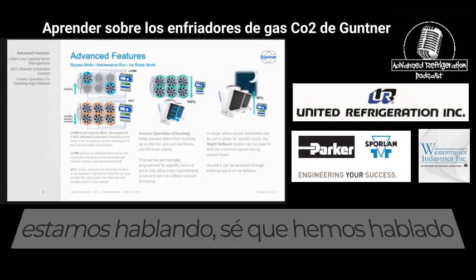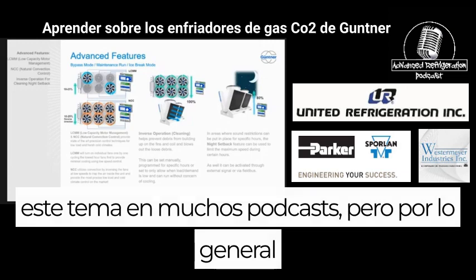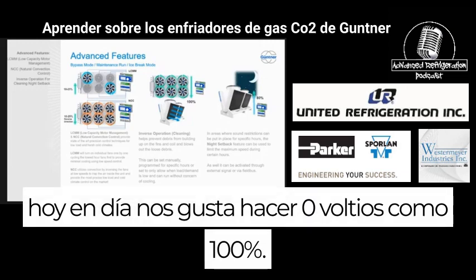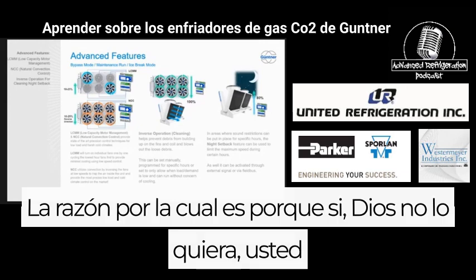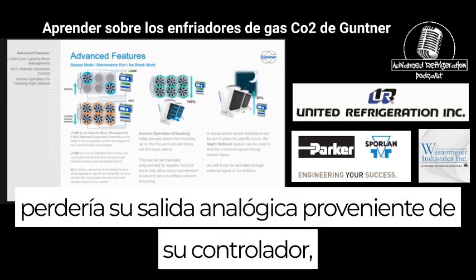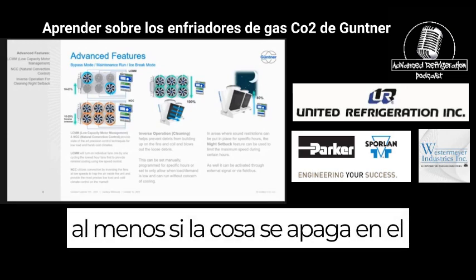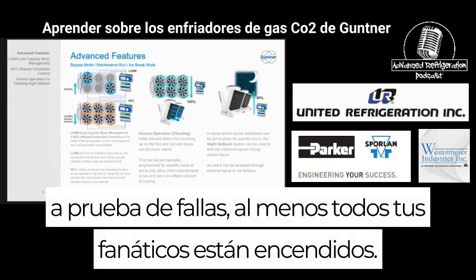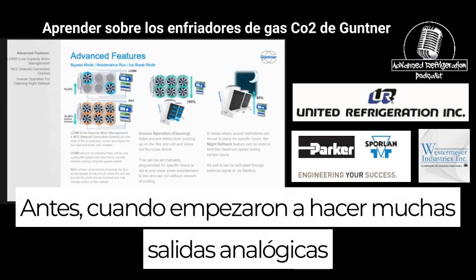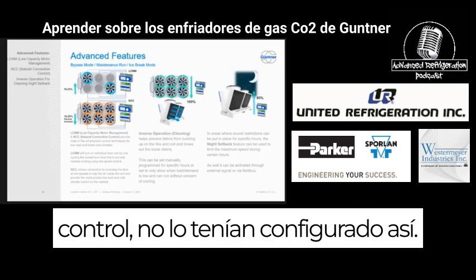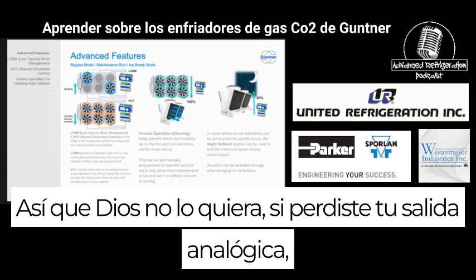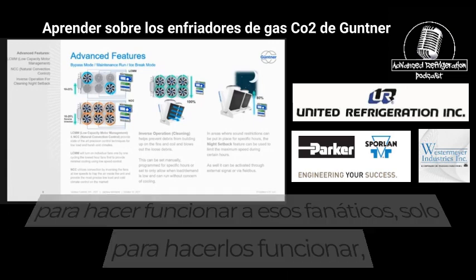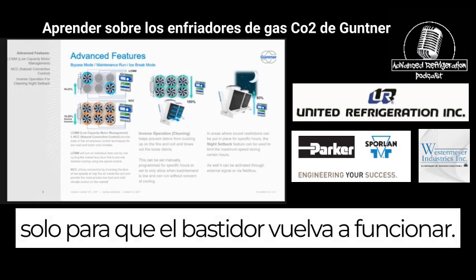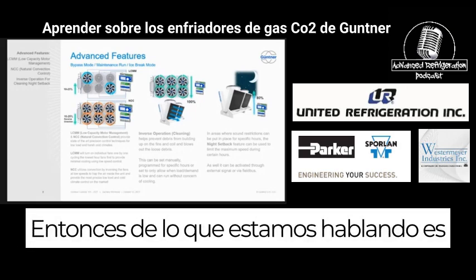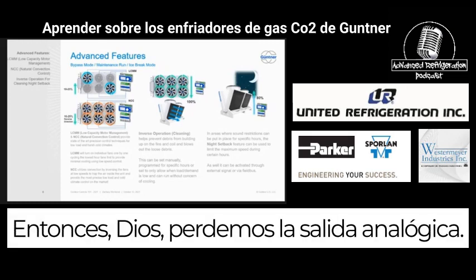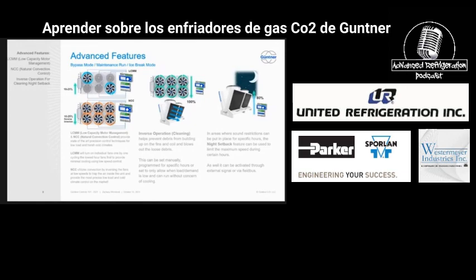So if you guys aren't familiar with what we're talking about, I know we've talked about this subject on many a podcast, but typically nowadays we like doing 0 volts as 100%. And the reason why is because if, God forbid, you would lose your analog output coming from your controller, at least if the thing shuts down, in the fail safe, all your fans are on. Back when they first started doing a lot of analog output control, they did not have it set up like that. So God forbid if you lost your analog output, you were looking for some kind of Hail Mary to get those fans running, just to get the rack back up and running. So what we're talking about is making sure it is inverted. So God forbid we do lose the analog out, we still have some fans rotating. Yep.